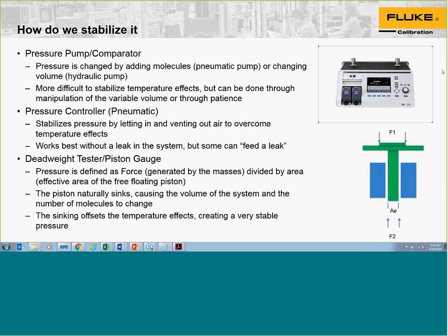The pressure goes slightly above the pressure you want to calibrate on and then you return it to the pressure. Do you mean turning the screw, or just waiting for the temperature to drop and consequently the pressure? Both. Yes, you turn the screw press and go slightly above the pressure that you want to go to. Temperature effects dissipate, the pressure will go slightly down, and you'll end up very close to the pressure that you need to attain. It's noted, especially on calibrating pressure transmitters, hitting the exact cardinal pressure is not really necessary as long as you record the actual pressure that you're taking your measurement at.